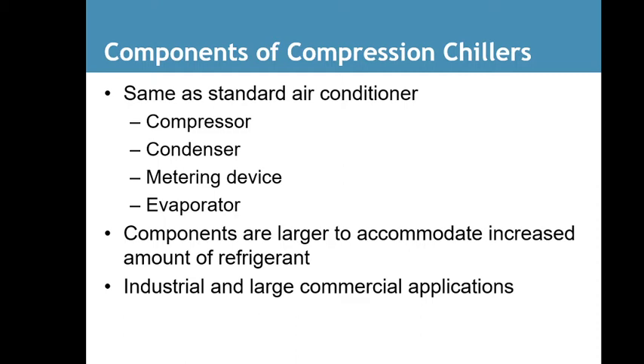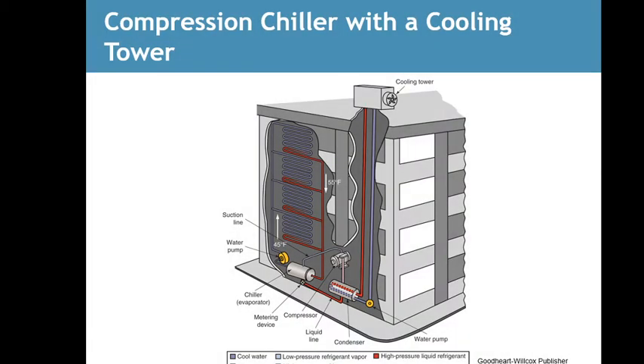Components of compression chillers are the same as standard air conditioners: compressor, condenser, metering device, and evaporators. Components are larger and accommodate an increased amount of refrigerant, for industrial and large commercial applications. Here's a diagram of a compression chiller. It's going to have pretty much the same components as an air conditioning system does, but it's not using air to cool and heat, it's using water. And you'll see more diagrams of these in your book.